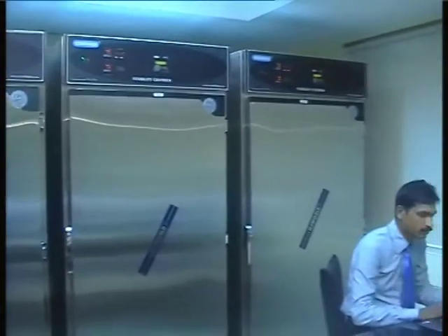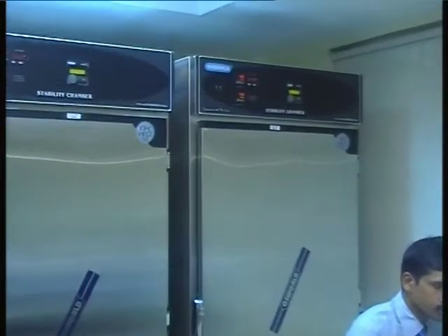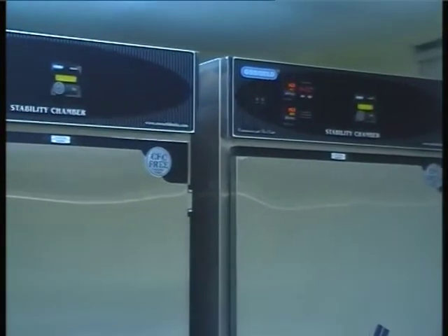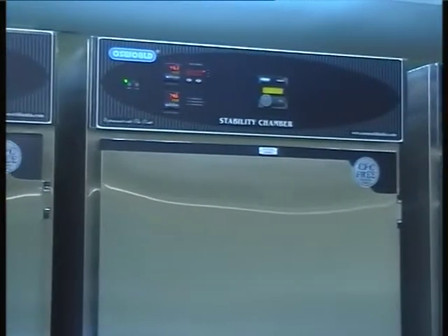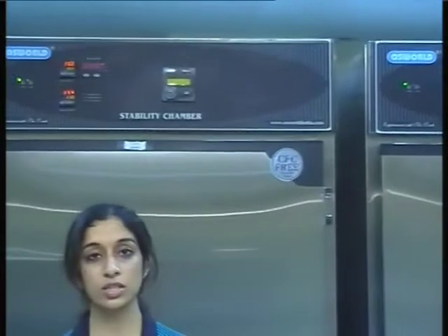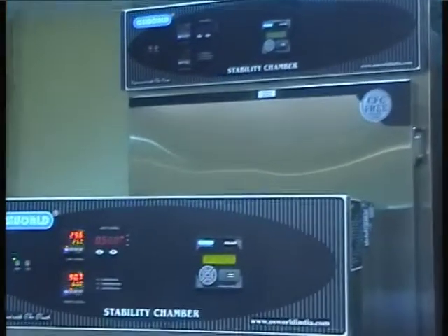There are certain problems that may arise due to use of poor quality water. Firstly, extensive scaling may occur on the low water level sensor, making it inoperational. This results in improper sensing of the water level, which causes the heater to burn out. High amounts of scaling can also occur on the heater casing, which damages the heater within 2 to 3 months of use. Problems may also arise due to high water inlet flow pressure.